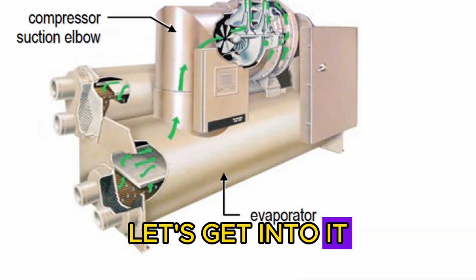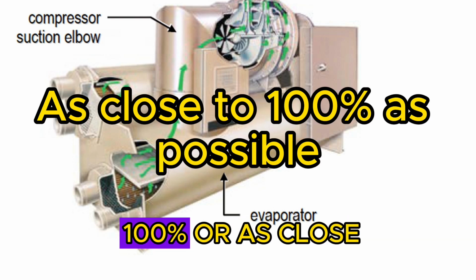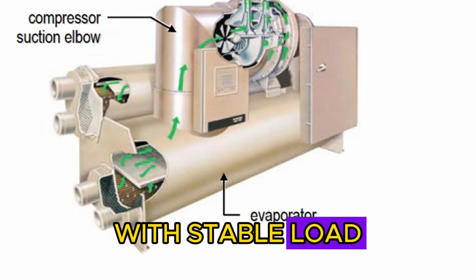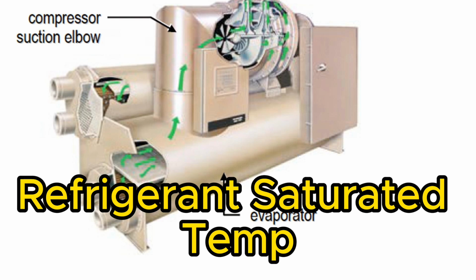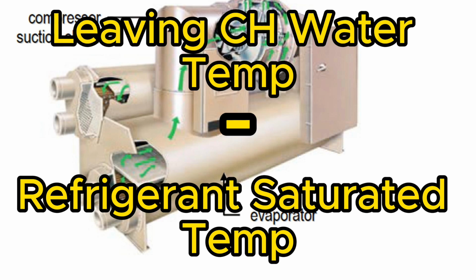Let's get into it. Run your machine at 100% or as close to it as possible with stable load. Take your refrigerant pressure and convert it to its saturated temperature using a PT chart. Next, simply subtract that temperature from the leaving chilled water temperature.